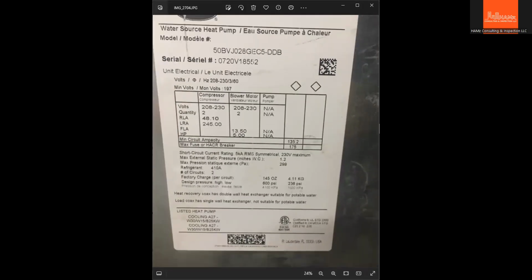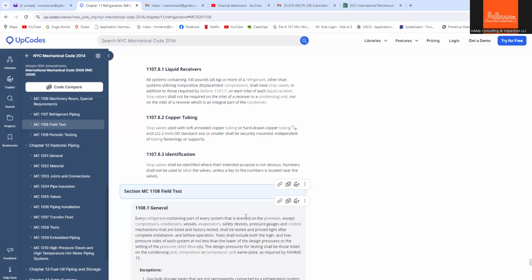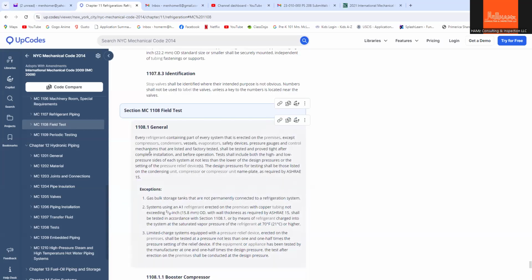So remember in the code, it says that every refrigerant containing part, every system that is erected in the premises, except compressors, condensers, vessels, evaporators, and safety devices. Oh yeah, you see, except those equipment that is tested by the manufacturer. Safety devices and pressure gauges should not be included in the test. So that's the exception.